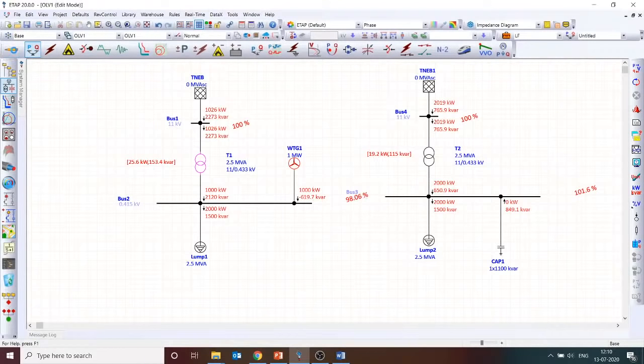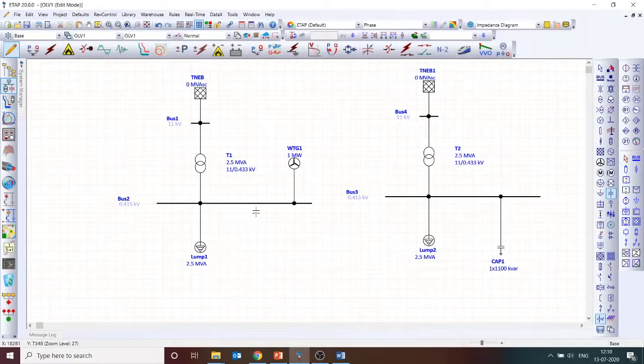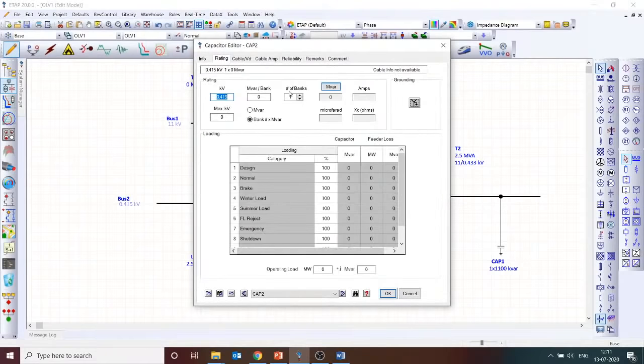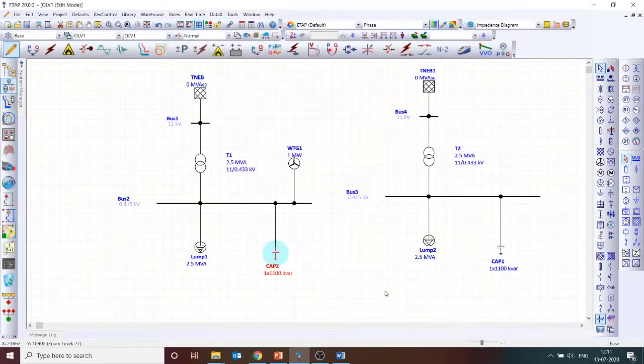Before concluding, let me talk about one more important aspect. With the same 1100 kVAR capacitor bank, with the wind turbine generator, what will be the impact? That's what I need to see. I'm going with the same 1100 kVAR capacitor bank at the same 480 volt. Intentionally, I have another question: why did I change this 415 volt to 480 volt? Here the bus voltage is only 415 volt, but for the capacitor bank I have changed it to 480 volt. Is there any specific reason? If you know the reason, you can answer it. If not, go to our channel and find power factor correction part 1 and part 2. You will get the answer there.